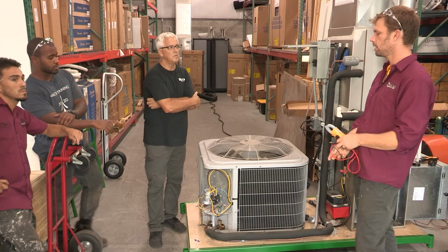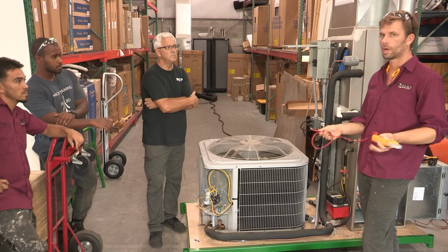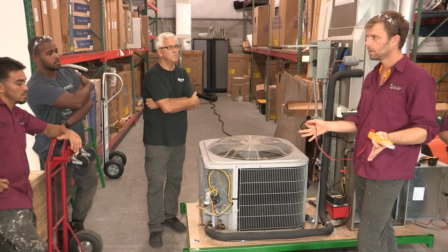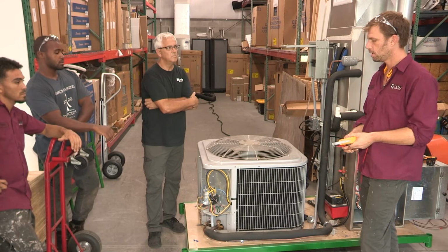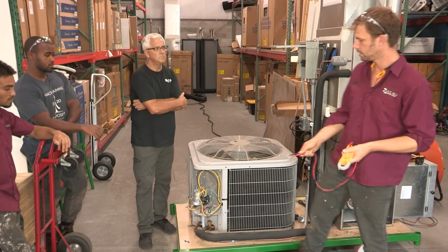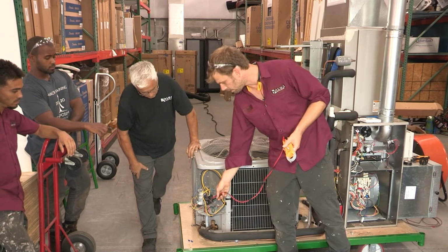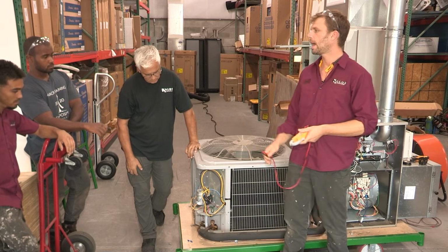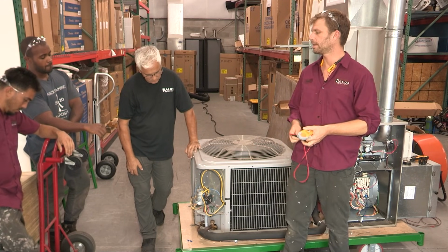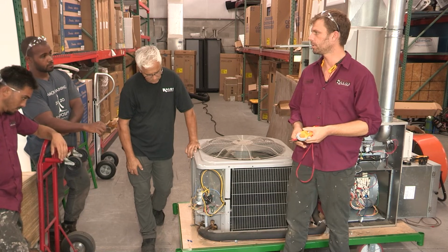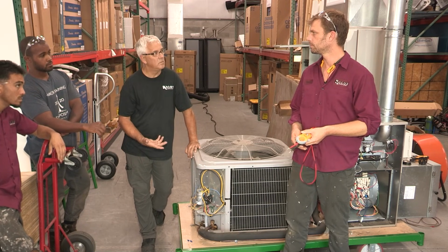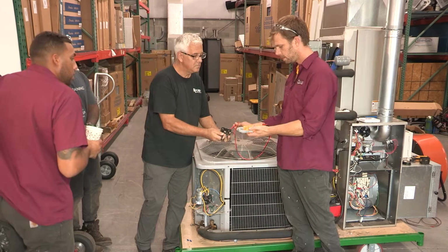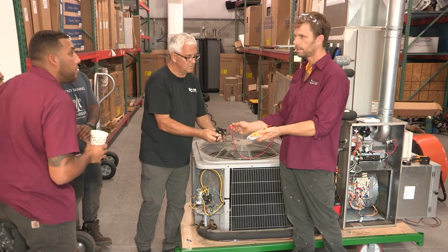Look for those points first, which is why we tested the ground first, because that's typically where you're going to see it. So since we've measured 0, we know that's wrong, but how might we figure out what a capacitor or a contactor coil should be? Testing a good one? Testing a good one. Do we have a good one? All right, so we got 14 across this, yep.